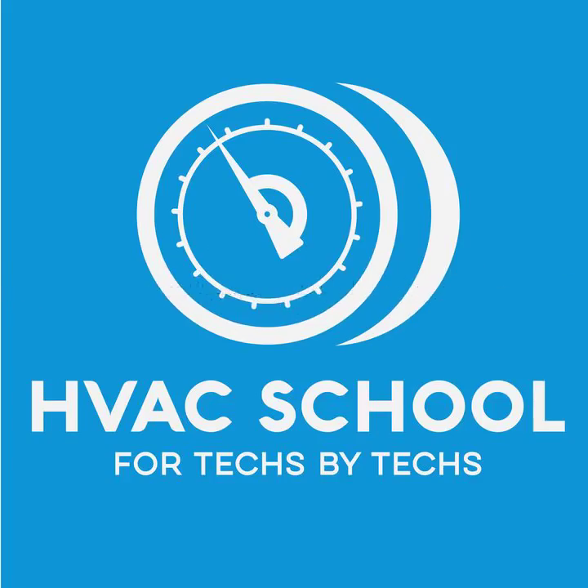You know, that's another segment of the industry that it's very difficult to verify system operation on the refrigerant side. I talk a lot about the Testo 605Is. They're just little digital thermohygrometers that are very accurate. You can use 2 of those and very quickly confirm how many BTUs a system is delivering, as long as you can, with at least reasonable accuracy, figure out what the airflow is. And like I said, with X13s and ECMs, that is a little easier than it used to be, at least.